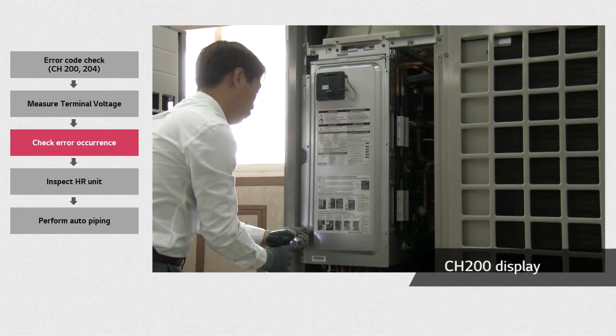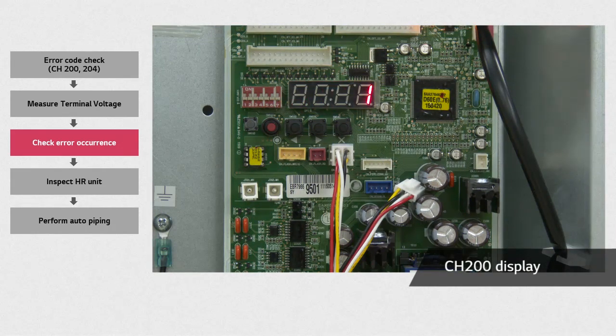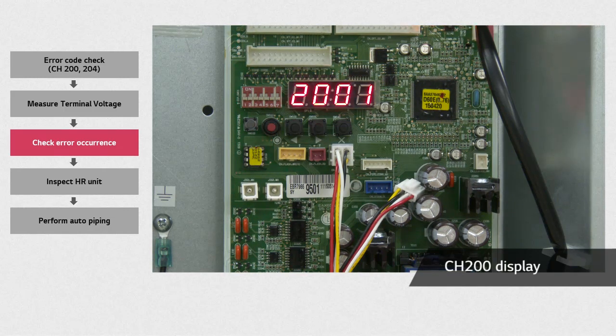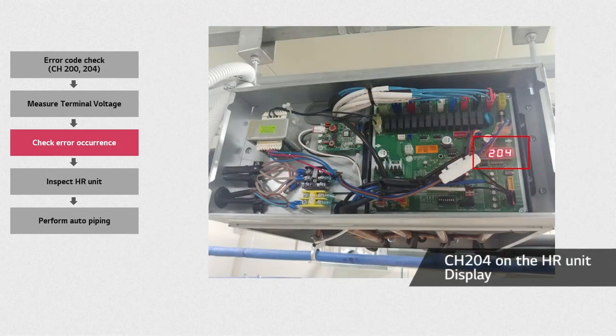Then disassemble the control box cover of the outdoor unit. You can check the error number on the ODU's PCB. If it is error CH200, the number 200 will be displayed on the PCB screen. You can also check if it is error CH204 by looking at the screen of the ODU's PCB — this is a communication error between the ODU and the HR unit. You can also check the error number at the HR unit's 7-segment display.